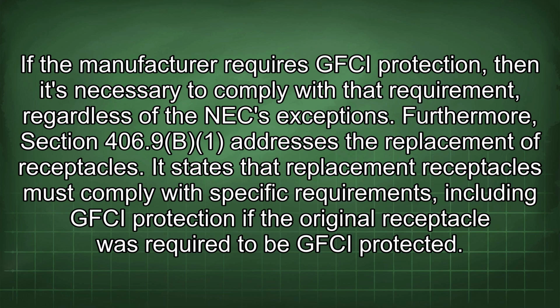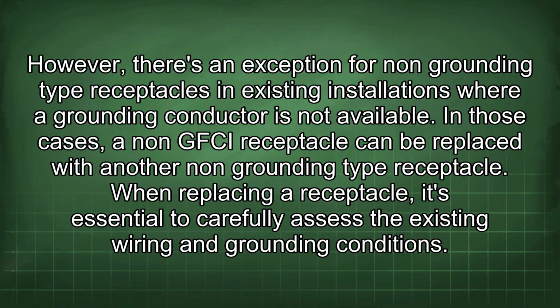Furthermore, Section 406.9(B) addresses the replacement of receptacles. It states that replacement receptacles must comply with specific requirements, including GFCI protection if the original receptacle was required to be GFCI protected. However, there's an exception for non-grounding type receptacles in existing installations where a grounding conductor is not available. In those cases, a non-GFCI receptacle can be replaced with another non-grounding type receptacle.